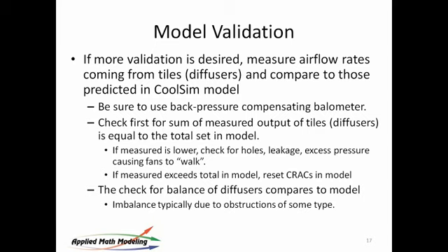First, look at the delta T's on the CRACs and make sure they're valid. Then take a look if you want to go further. Oftentimes, delta T's on the CRACs are enough, because you've captured the physics. You're just looking for rough parameters. You're trying to get your hands around the big things. But if you want to go further, then measure the flow rates. And first, the totals need to match. The total being measured needs to equal the total being delivered in your model. And then look at distribution.